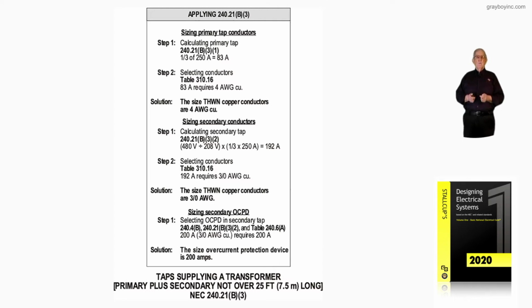Now, let's review step one. Step one, we're calculating the size of the tap for the primary, and it would be 1/3 of the overcurrent device, which would be 83 amps. If that still was a 600 amp overcurrent device, it'd be 1/3 of 600, and the primary tap would have to be at least 200 amps. So keeping in mind now, it's the overcurrent device that determines the size of these taps, primary or secondary transformer conductors.